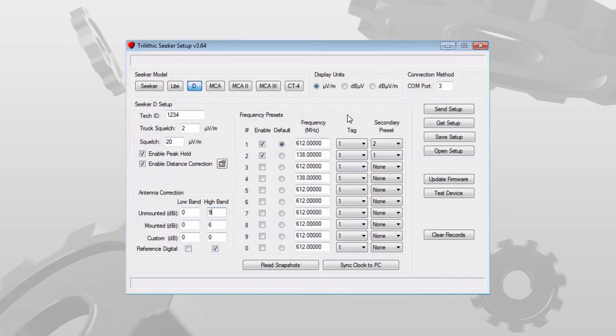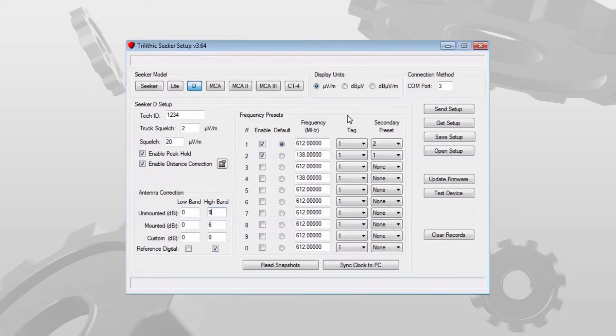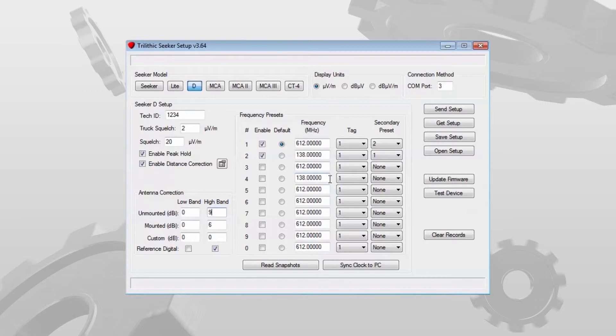If I have a Seeker D that I want to see what its current programming is, maybe I suspect it's got the wrong frequency or the wrong tech ID, I can connect to it and hit get setup and it will populate all these fields with the current settings in the Seeker D.